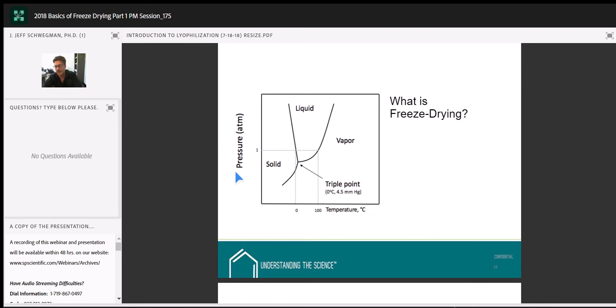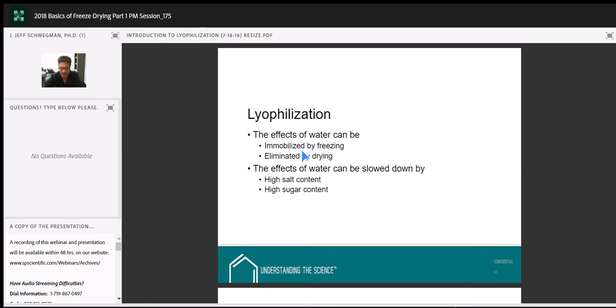So why does lyophilization work? Sublimation is the chemistry term for changing directly from the solid state to the vapor state without going through the liquid state. Ice sublimes in an attempt to achieve vapor equilibrium. When the chamber pressure equals the ice vapor pressure, sublimation stops. Everything has a vapor pressure: for example, if you take a vial of water, put a pressure sensor in the headspace, and put a lid on it, you'd see a rise in pressure as water molecules leave the surface and go into the vapor state.